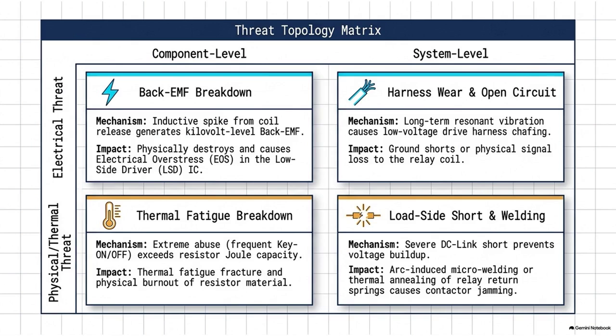So because the control switch on the motherboard cuts the current in a matter of nanoseconds, the rate of change is astronomical. Even if the coil is small, the resulting voltage spike is just massive. We're talking kilovolt-level transients. Thousands of volts ringing back down that tiny 12-volt control wire, heading directly into the battery management system motherboard. So if the low-voltage circuit isn't protected, this kilovolt spike punches right through the silicon. Exactly. It hits the low-side driver IC, the silicon switch that commanded the circuit in the first place, and it exceeds the dielectric breakdown voltage of the silicon lattice. It just fries the chip.